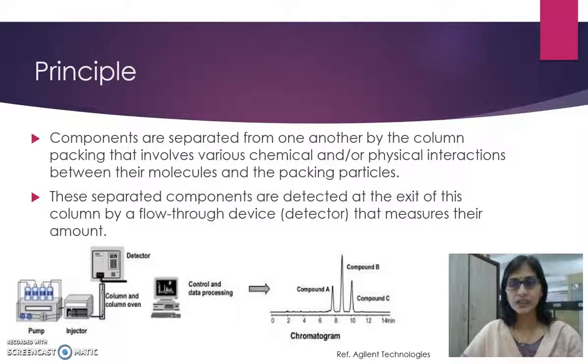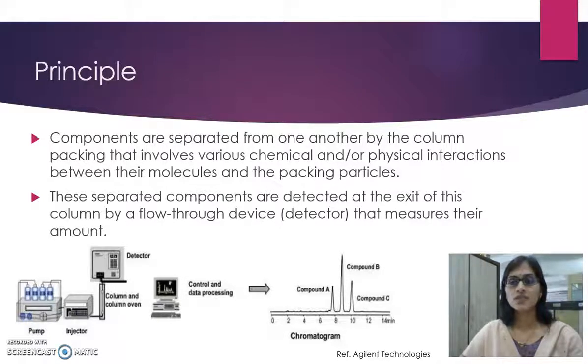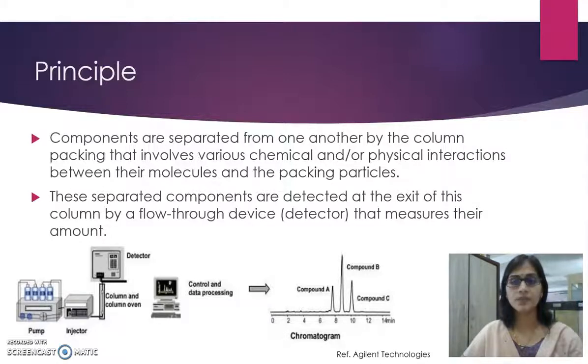HPLC is a separation technique that involves the injection of a small volume of liquid sample into a column packed with tiny particles. The particle size is around 3 to 5 microns in diameter. It is called the stationary phase, where individual components of the sample are moved down the packed column with a liquid called the mobile phase, which is forced through the column by high pressure delivered by a pump. These components are separated from one another by the column packing that involves various chemical and/or physical interactions between their molecules and the packing particles.